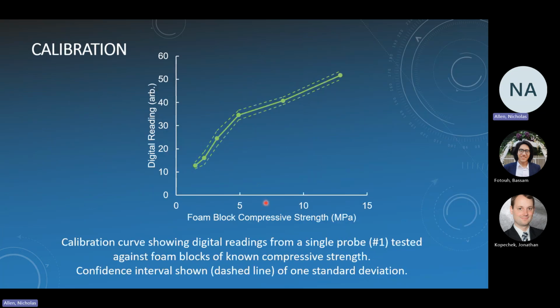Here's an example calibration curve of probe number 1. I forget, there's at least 10 holes for each of these points, if not more. Is that about right? 10 holes, an average of 100 measurements taken from each. Okay, so yeah, 10 measurements per hole, 10 holes. So this is our calibration curve, and it's not as we would like it to be. But it was fairly consistent. Like this one maybe dips down a bit, and it's not linear.